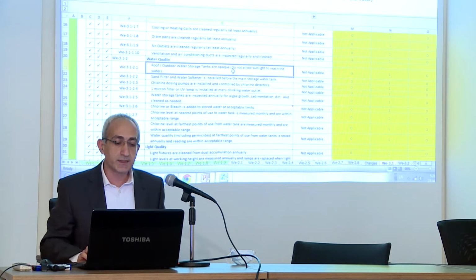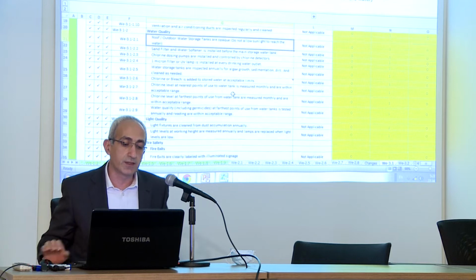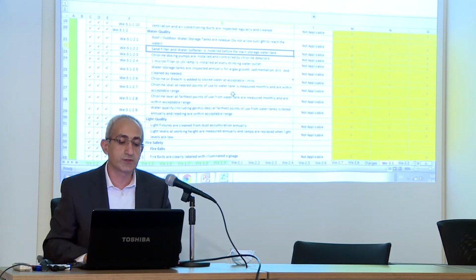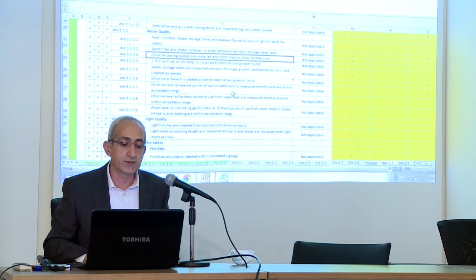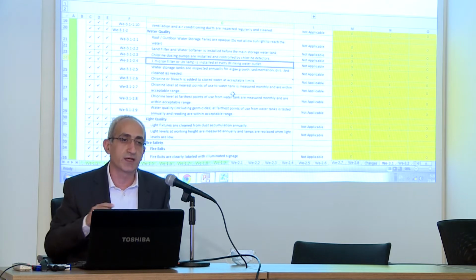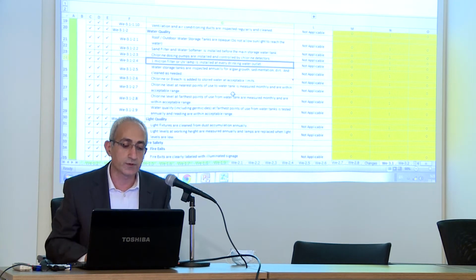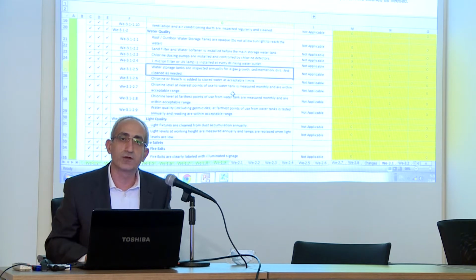We come to water quality. Similarly, we're asking for the roof and outdoor water storage to be opaque. Sand filters and water softeners properly maintained. Chlorine dosing pumps properly maintained. A 1 micron filter or a UV lamp is installed at every drinking outlet. Not applicable if you're using another item of water filtration. Also, water storage tanks are inspected annually and cleaned from sedimentation, dirt, and other debris. Water tanks tend to be ignored completely.